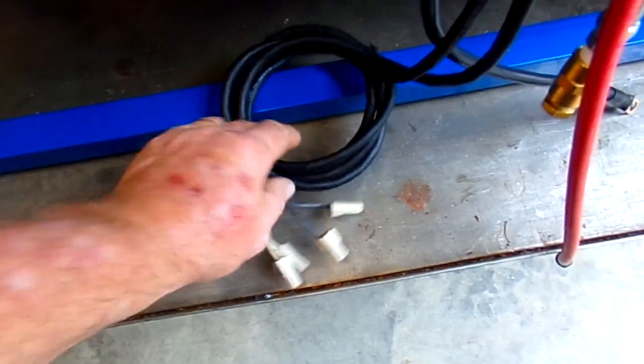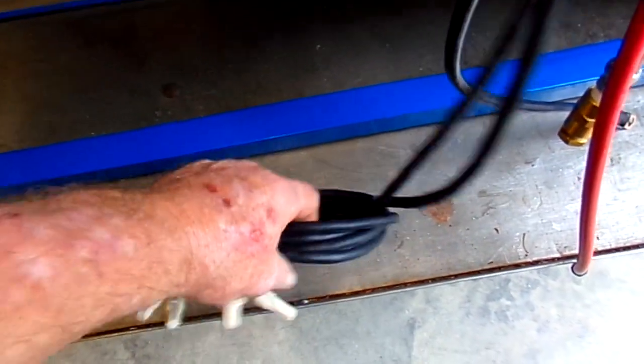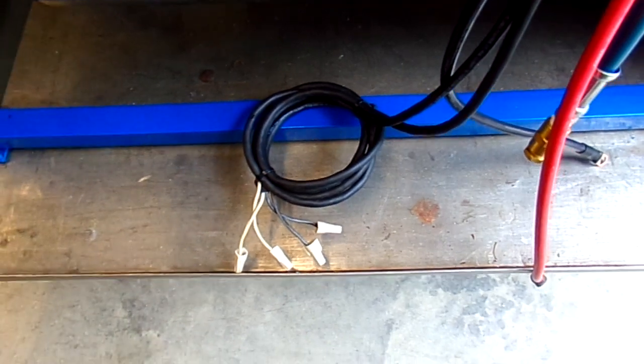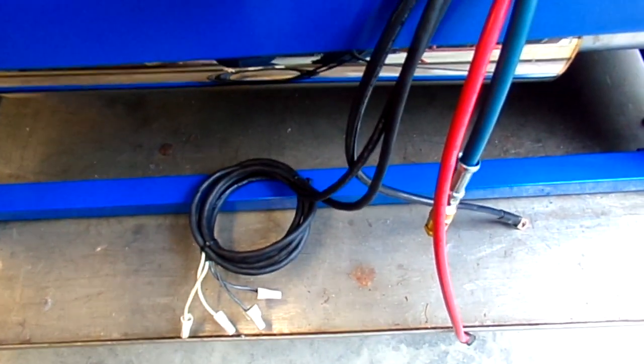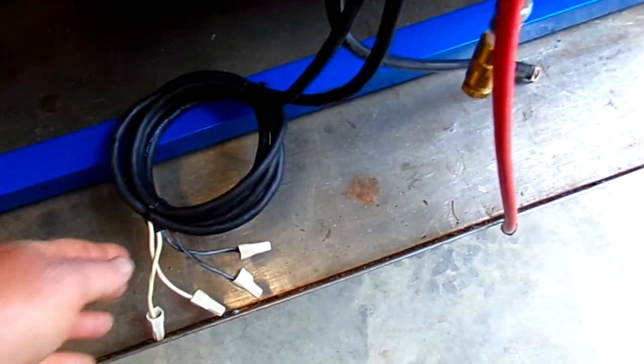You've got this tied right now, but it can be flopped over, and you put a pan at the bottom and let it drain out. You've got power cables, one which is the high limit shutdown for your wastewater tank in case it gets too high, there's a liquid level switch on the tank, as well as another set of wires that controls your solenoid on your unit.